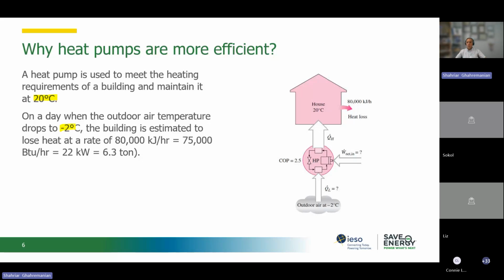Let's assume that the temperature outside is -2 degrees Celsius. Thank God, this week is super hot. It's good actually, but the winter is coming soon. So it's going to be -2 degrees Celsius outside. Based on the evaluation, this building requires 80,000 kilojoules per hour, which is equal to 75,000 BTU per hour or 22 kilowatts or 6.3 tons of heating.